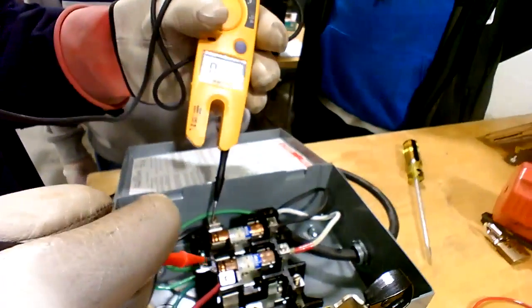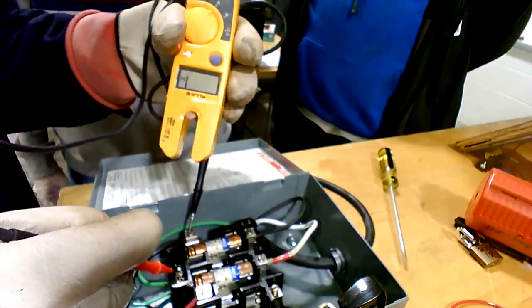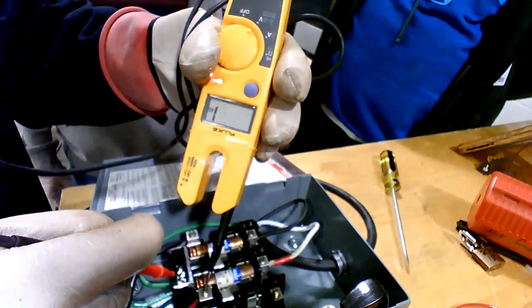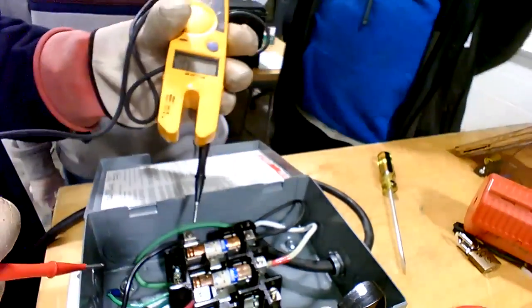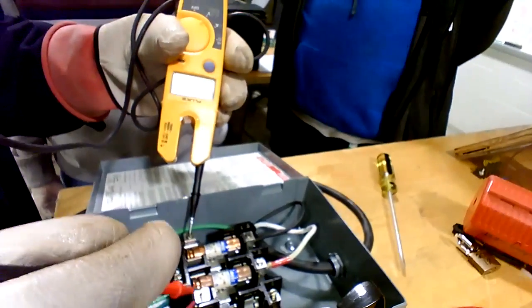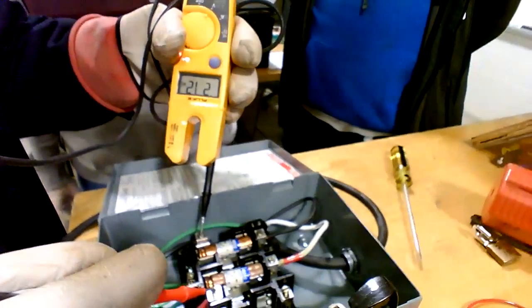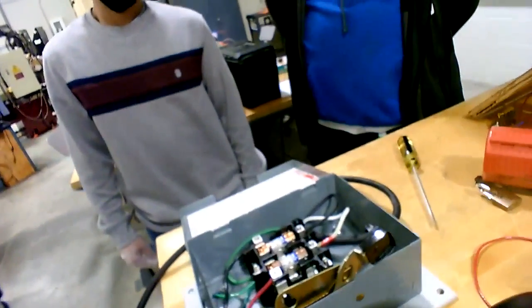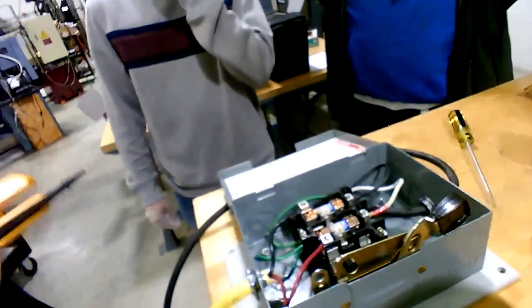Yeah, you're going to check the outgoing two lines. Well, you can go to the ground on each one of them. Should be 120. And now check leg to leg on the fuse. Yeah, that's correct. You get about 212. Yeah, that's good. So that's how you can diagnose it going through your disconnect, and now you're gonna check the amps.